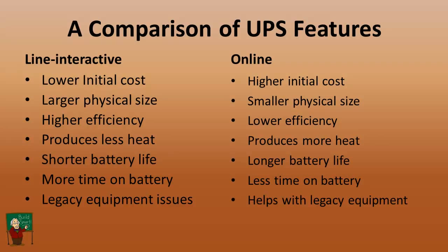Line interactive is typically found in 5 kVA and under. Online is available in those sizes, but beyond that, the online is the more common UPS.